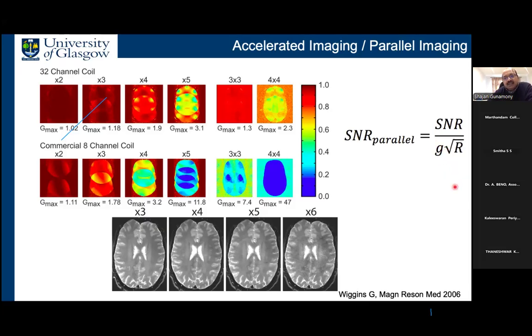And G is a factor called the geometry factor, which is related to the coil. We want this G factor to be close to 1. Then the penalty you pay is less. So here in this plot, you see the comparison between an 8-channel coil and a 32-channel coil. The G factor of a 32-channel coil is always less than a G factor of an 8-channel coil. That's how it helps in this parallel imaging.